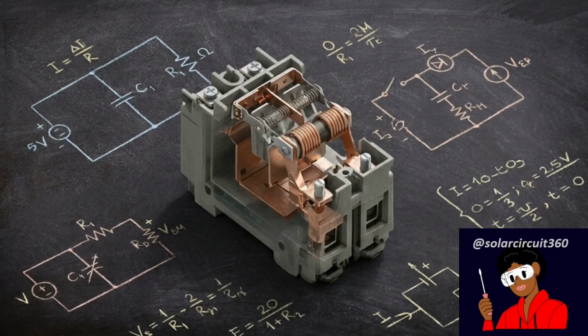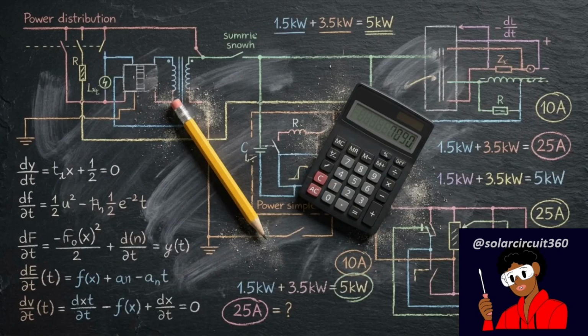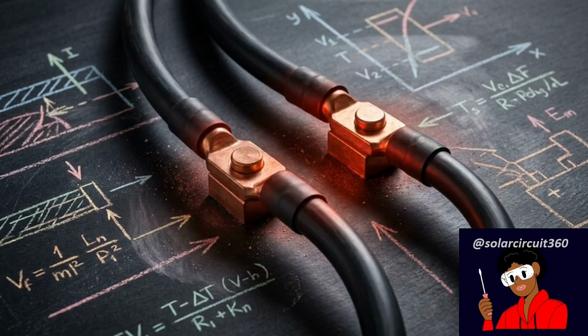The reality is that breakers and internal components respond to two intersecting variables: the magnitude of the current and the duration it is applied. Many DIY installers misdiagnose their power systems because they calculate their power needs on paper, but fail to account for the physical, thermal limits of a low-voltage, high-current environment.